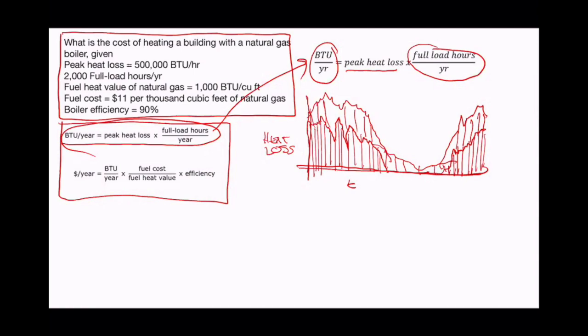One way to look at that is in terms of what's called full load hours, which is just what it sounds like. It's based on the peak heat loss—say the peak heat loss we designed for is right here. We can say we're using enough fuel to be equivalent to running the system full time for some number of hours. That area, the distance on the x-axis of time, is our full load hours.